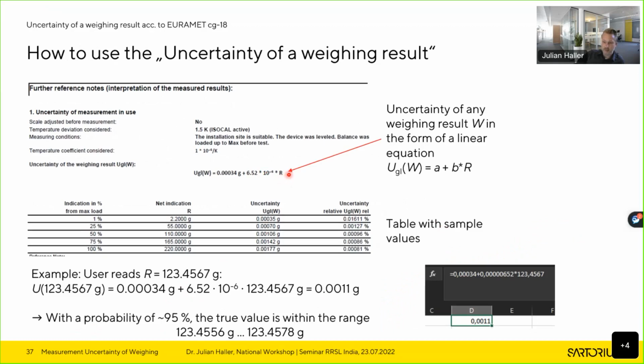Well, actually, it's quite simple. If the user reads a reading, whatever, 123.4567 grams, they can simply put that value into the equation. So the uncertainty of this reading would be this value, the alpha, plus the beta multiplied with the reading. You can use, for example, Excel or a calculator to calculate that the uncertainty for this reading is 0.0011 gram. And that just means, again, with a probability of 95%, the true value is within the range reading minus uncertainty to reading plus uncertainty.